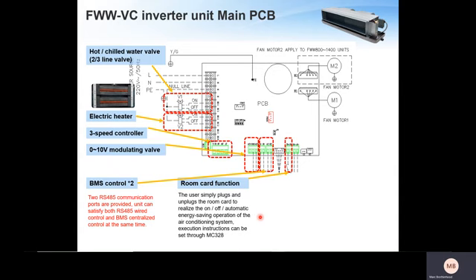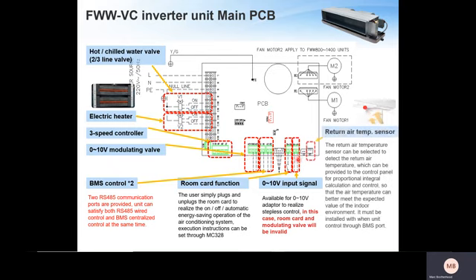You have a room function card here, ideal for hotels. So your hotel access card, or you could even have like your window kill switch, your make or break. If they open a window, the fan can stop on this unit to not waste any air conditioned air. Here is your 0 to 10 volt linear signal. If this is selected though, the room card and modulating valves will be invalid. So you won't be able to use your 0 to 10 and your window card. This takes priority to drive the fan motor.